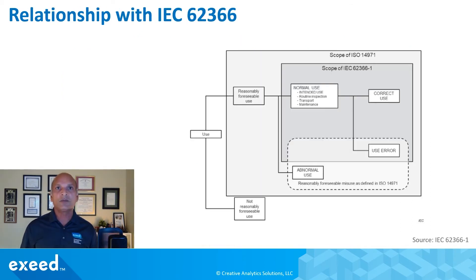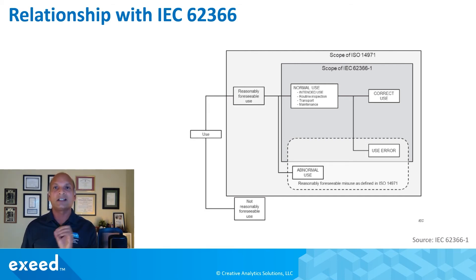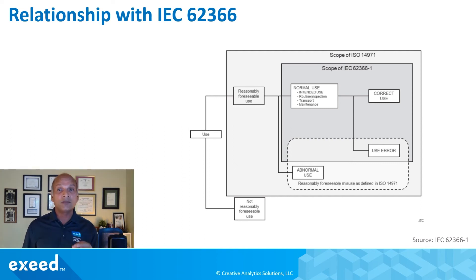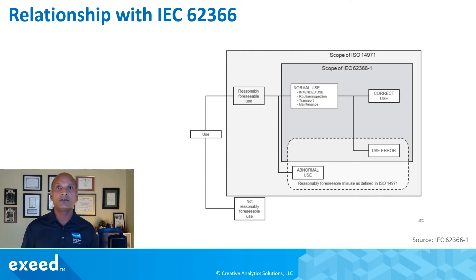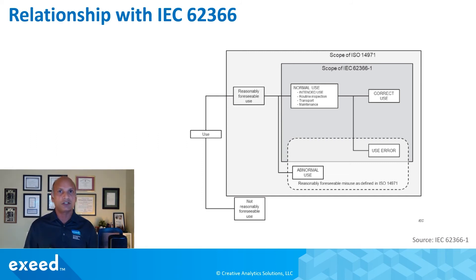Here's the relationship with IEC 62366 — a pretty insightful chart taken directly from the IEC standard. From an IEC point of view, they distinguish normal use and correct use from use error and abnormal use. Both use error and abnormal use are within the scope of ISO 14971. Abnormal use is an intentional, deliberate decision to use a device differently from what the manufacturer intends — for example, a surgeon using your product for a different indication. We need to clearly separate use error from abnormal use in our analysis.